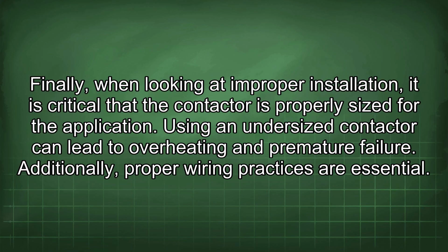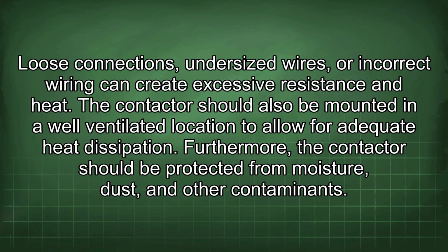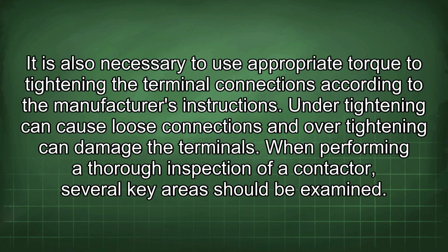Using an undersized contactor can lead to overheating and premature failure. Additionally, proper wiring practices are essential. Loose connections, undersized wires, or incorrect wiring can create excessive resistance and heat. The contactor should also be mounted in a well-ventilated location to allow for adequate heat dissipation. Furthermore, the contactor should be protected from moisture, dust, and other contaminants. It is also necessary to use appropriate torque when tightening the terminal connections according to the manufacturer's instructions. Under-tightening can cause loose connections and over-tightening can damage the terminals.